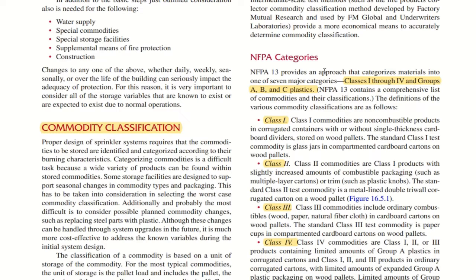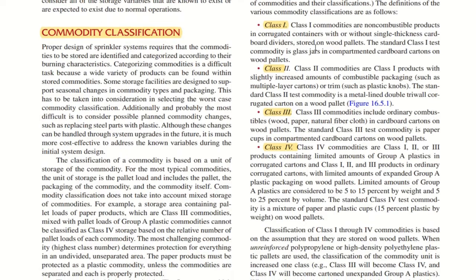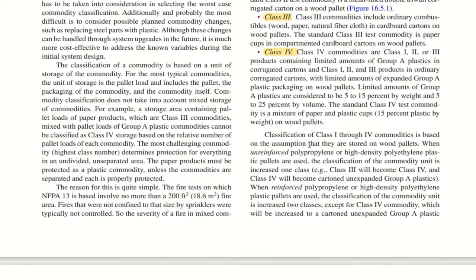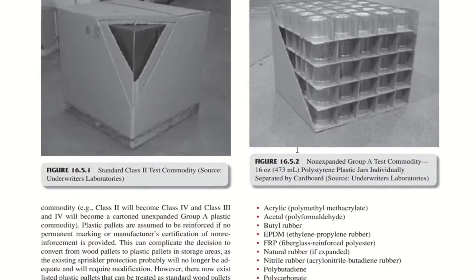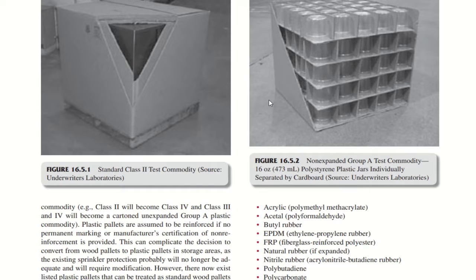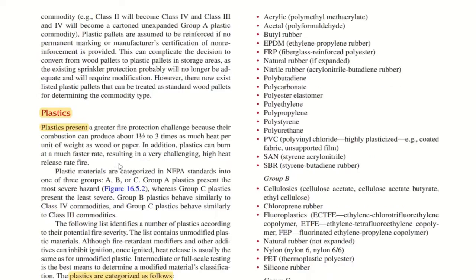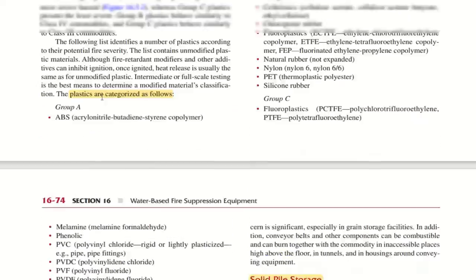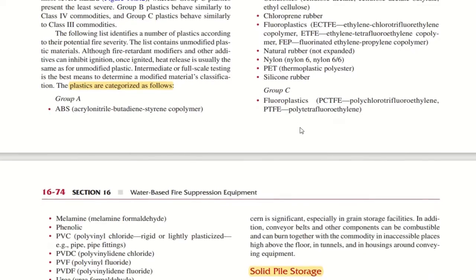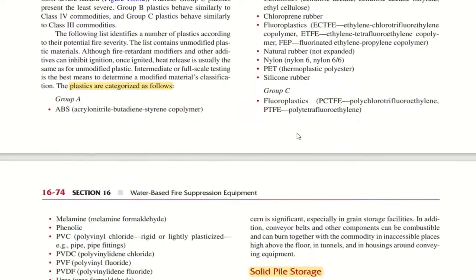NFPA 13 provides an approach that categorizes materials into one of 7 major categories: classes 1 through 4 and groups A, B and C plastics. Here class 1, class 2, class 3 and class 4 type of commodities. Based on these commodities the sprinklers shall be defined. So you have plastics, you have group A plastics, group B, group C plastics as well. Some of the examples are mentioned here.